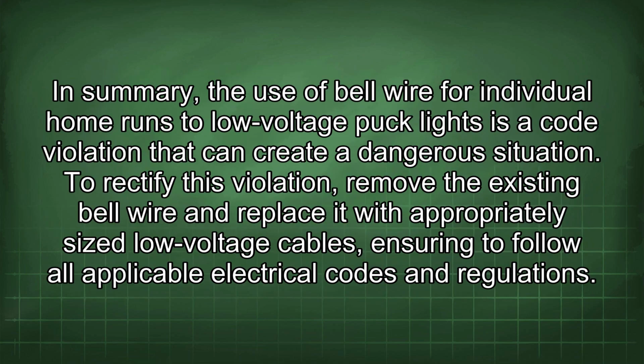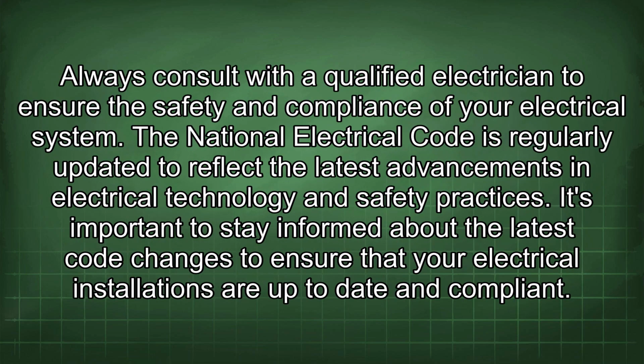In summary, the use of bell wire for individual home runs to low-voltage puck lights is a code violation that can create a dangerous situation. To rectify this violation, remove the existing bell wire and replace it with appropriately sized low-voltage cables, ensuring to follow all applicable electrical codes and regulations. Always consult with a qualified electrician to ensure the safety and compliance of your electrical system.